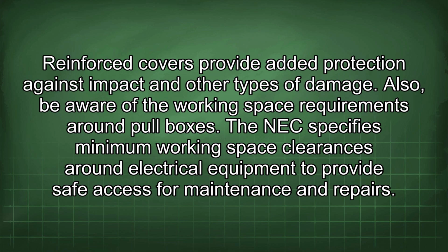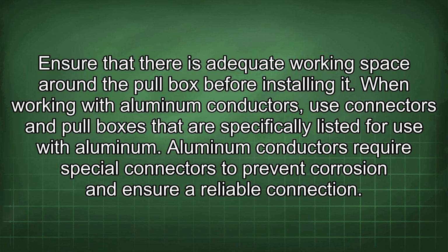Also, be aware of the working space requirements around pull boxes. The NEC specifies minimum working space clearances around electrical equipment to provide safe access for maintenance and repairs. Ensure that there is adequate working space around the pull box before installing it. When working with aluminum conductors, use connectors and pull boxes that are specifically listed for use with aluminum. Aluminum conductors require special connectors to prevent corrosion and ensure a reliable connection.